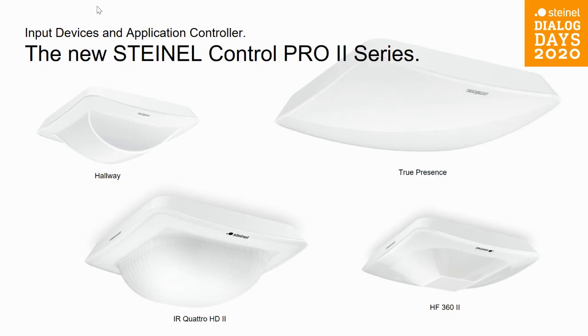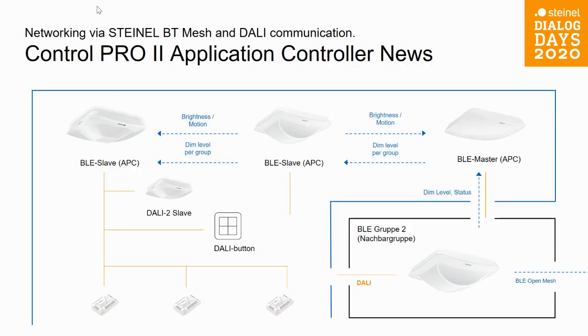The new STEINEL Control Pro 2 series as an application controller. So here we can see the networking via the STEINEL Bluetooth mesh and DALI communication. So there is now no need to run individual cabling between application controllers or input devices by using the Bluetooth interconnection. We can see the brightness and motion going from the middle sensor and the dim detection to the application controller on the left, and then interconnection to the DALI-2 slave and DALI push buttons to the control gear. This makes a simple, less overwhelming configuration for the integrators.